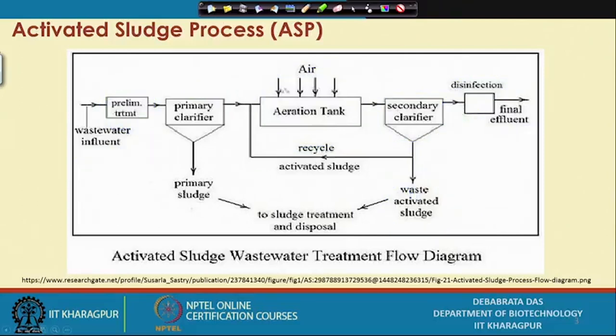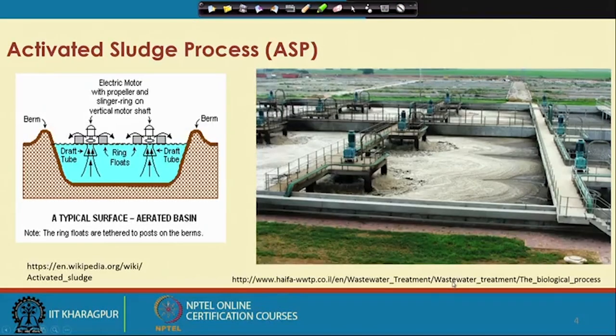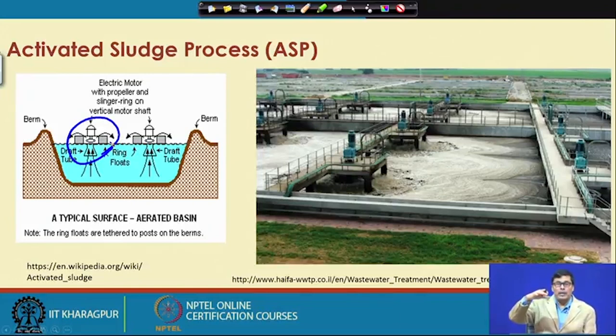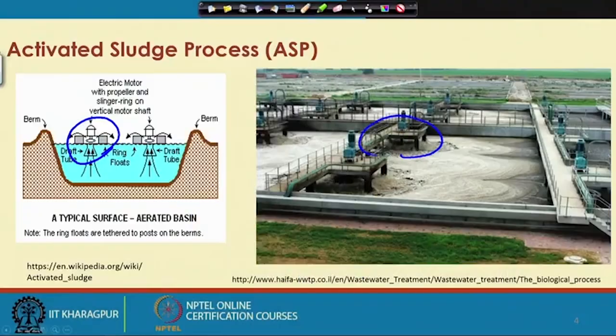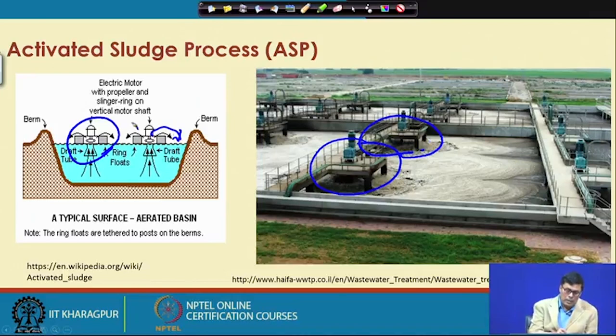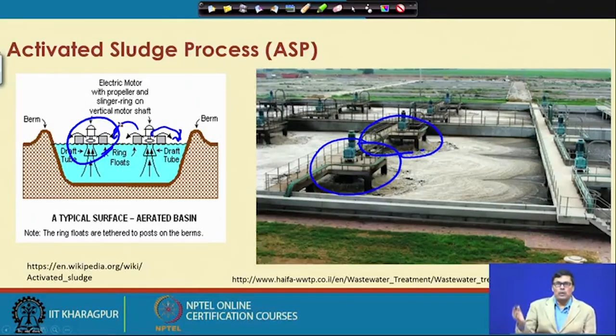Basically, the activated sludge process is a CSTR with cell mass recycling. In practice in the industry, a surface aerator floats at the top of the liquid. You can see how the surface aerator is located in the actual activated sludge process — it throws the water outward so that air comes in contact with the water, and more air contact with the water increases the dissolved oxygen concentration. When dissolved oxygen increases, the organisms grow more and can utilize more soluble organic material, and degradation of organic matter will be more — which is most desirable.